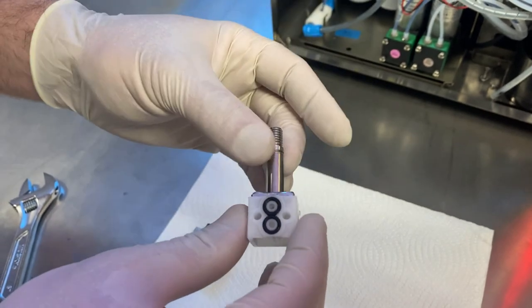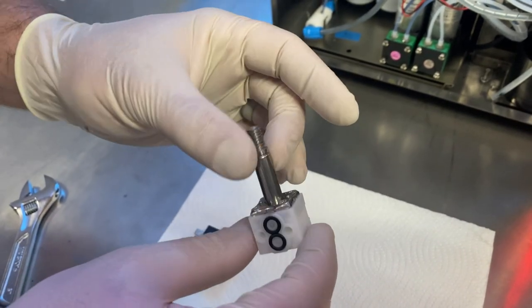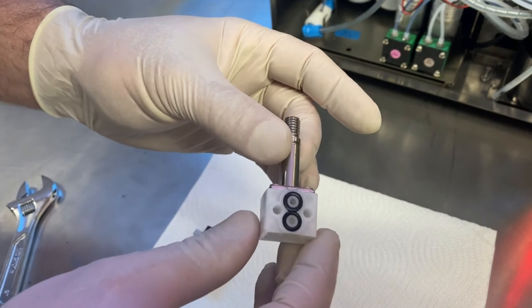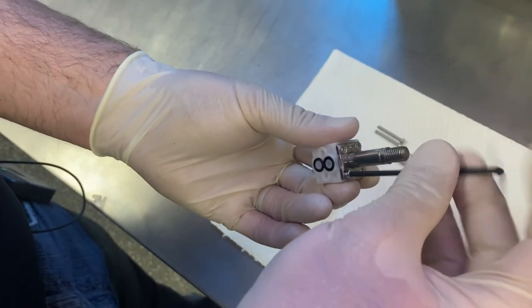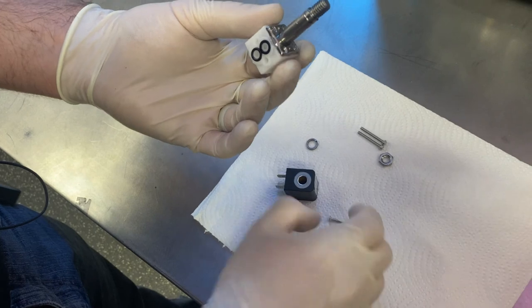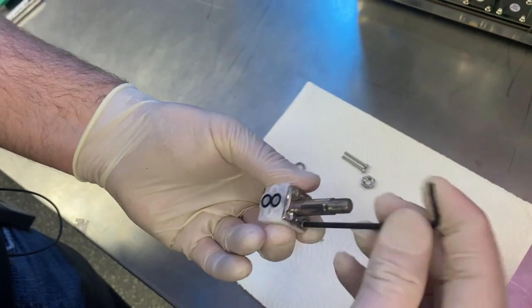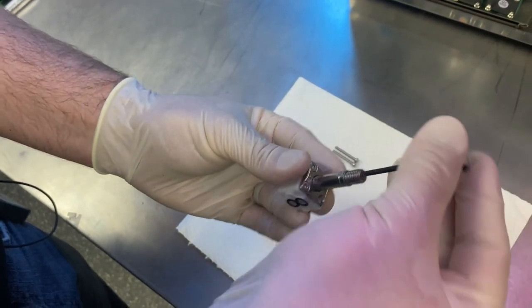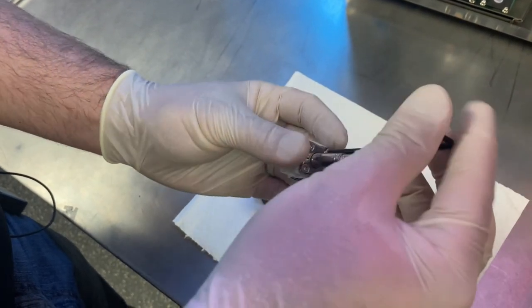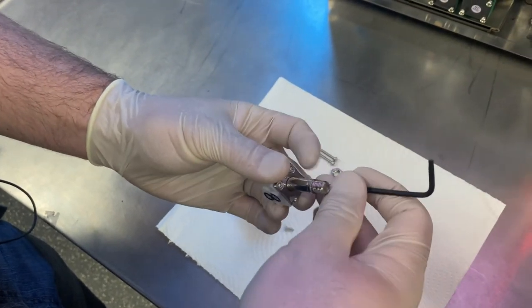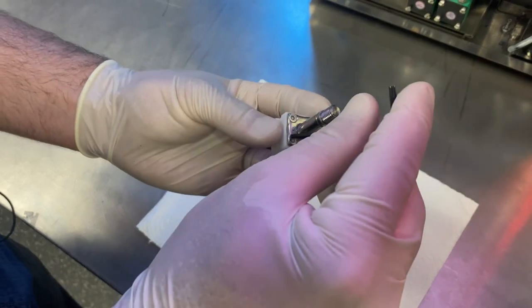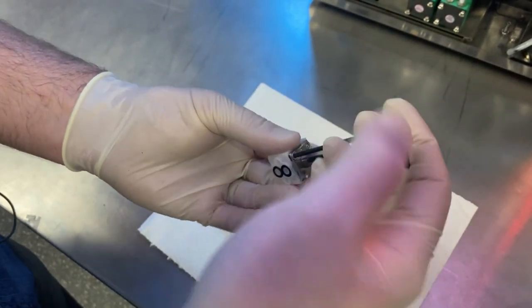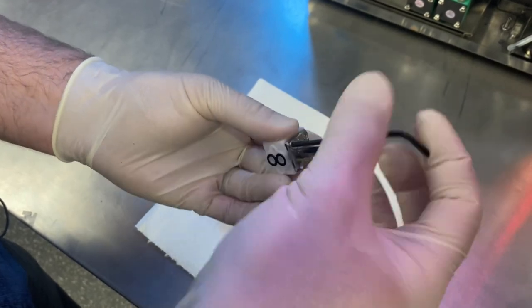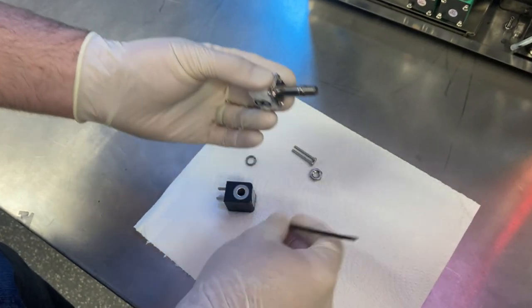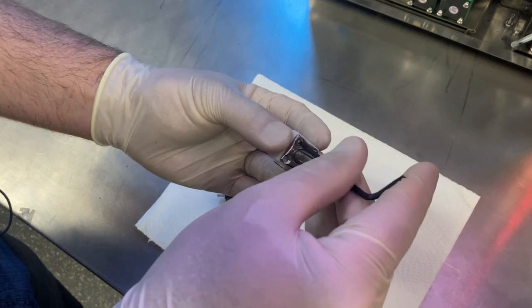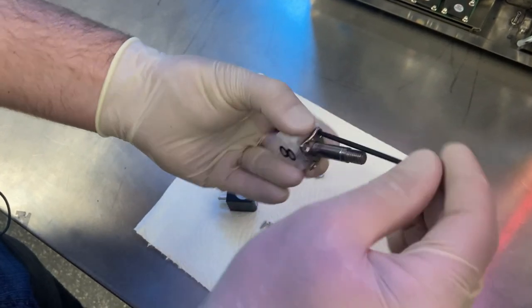So we'll open this up, show you how it looks, show you how it should operate, and that's about it. So again, we're just gonna take off the plunger housing really quick. One thing you'll see again with these makeup valves is they're perfectly clean. They only ever handle makeup, so there's no mess. Really, these are not failure points, but it's still good for you guys to see how they work and what they look like on the inside. So again, this is the exact same process as what we did with valve six as far as getting the plunger housing off, just with a little bit different internals.